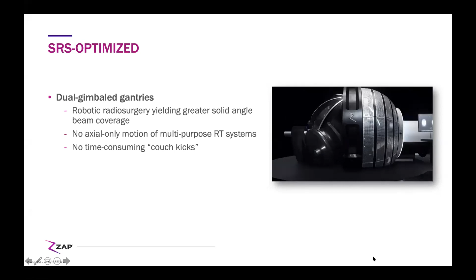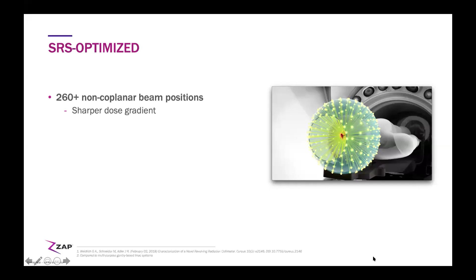And so what this means is that we've optimized every attribute of radiation energy and radiation crossfire to give you the proverbial sharpest knife. For starters, we have 260 or more non-coplanar beams that crossfire at a common point. We have optimized the energy, so there's less lateral scatter, again, steeper dose gradient. There is a collimation system that is just almost leakless. Now, I'm exaggerating some, but the fact is that it's 50 times more effective in stopping primary scatter off the target than your typical multi-leaf collimator, 50 times.